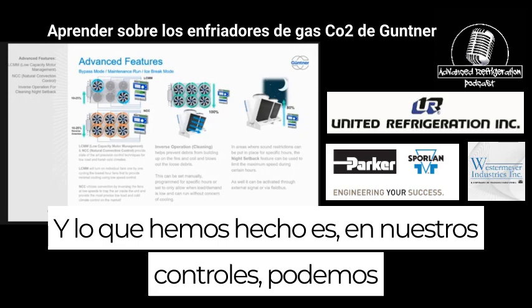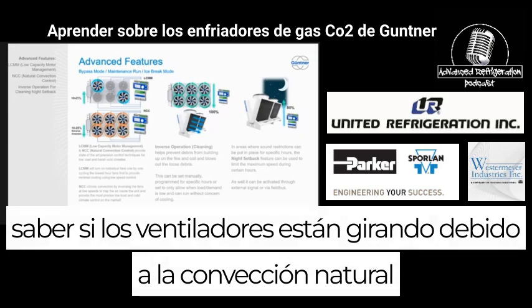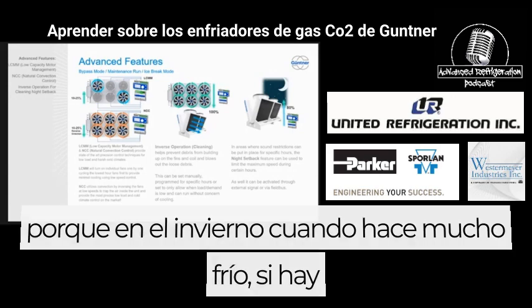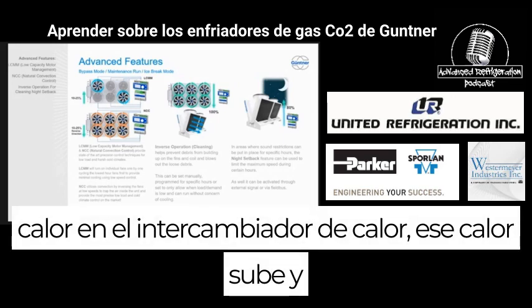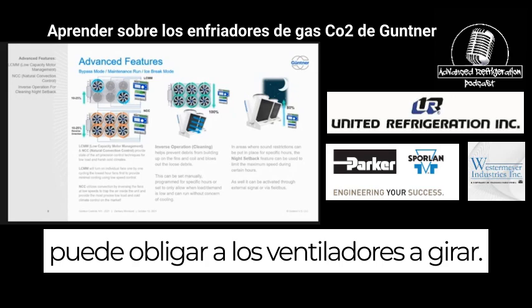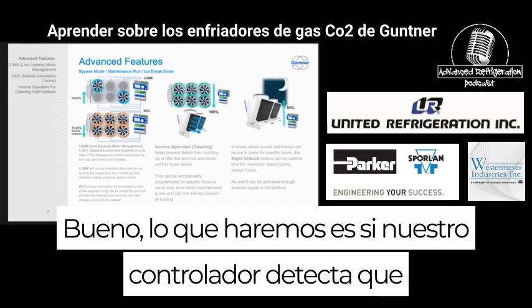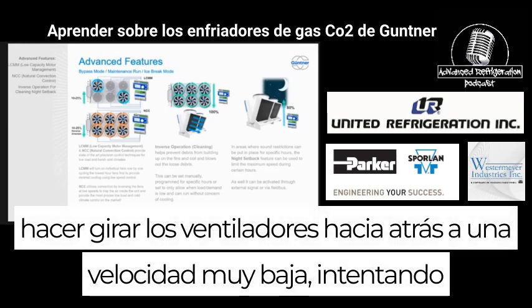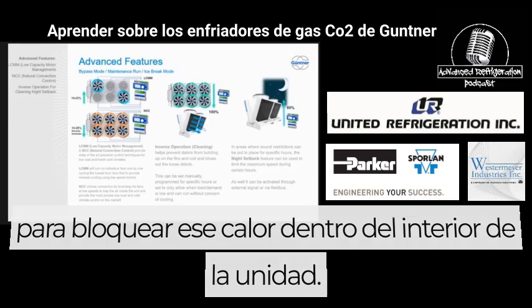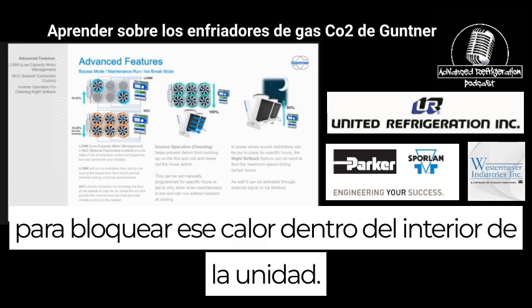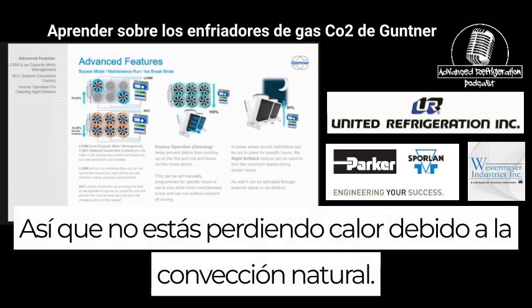And what we've done is, in our controls, we can tell if the fans are spinning due to natural convection. Because in the winter, when it's really cold, if there's heat in the heat exchanger, that heat goes up and can force the fans to spin. Well, what we'll do is, if our controller senses that, it'll actually spin the fans backwards at a very low speed, trying to lock that heat inside the unit, so you're not losing heat due to natural convection.